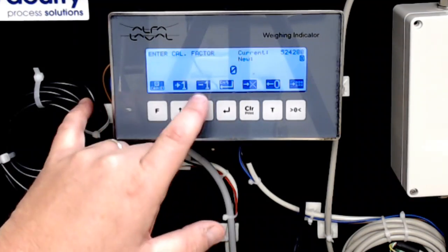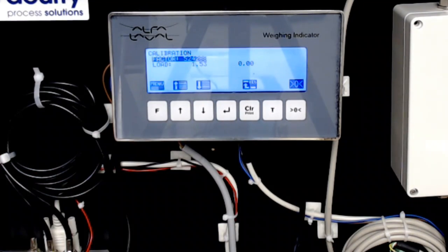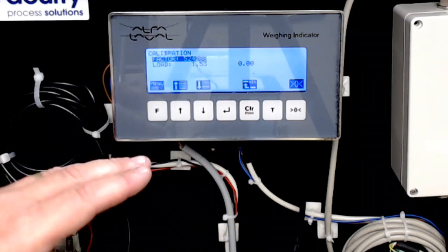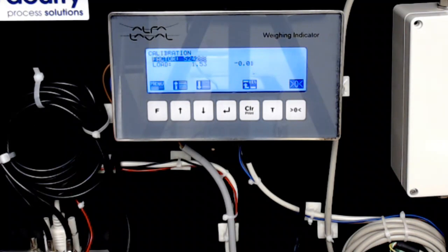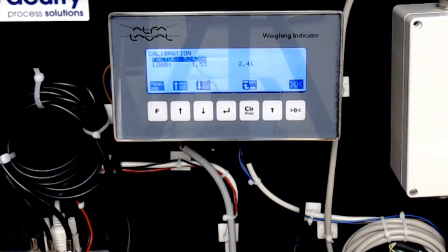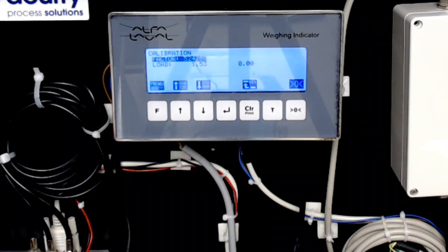If you wanted to just arbitrarily change it, you could enter here and enter a different calibration factor and change it. But that's not what we're doing here today. We're going to show you how to actually go through a correct calibration. So now you'll notice that there's nothing sitting on the load cells. That number right there is actually reading. Watch, if I push on this, since we've coarse tared, the camera's sitting on them, but we just told the system to forget about the camera. Okay, so now it's reading 0.